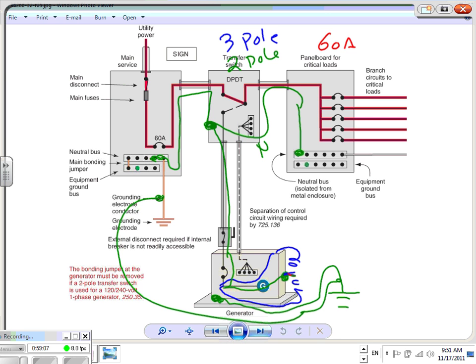A separately derived system. Any questions, guys, about this? Which one should I do? Either way. What's the advantage of doing it this way? Cheaper equipment. Instead of a 3-pole circuit breaker, you're using a 2-pole circuit breaker. Instead of a 3-pole transfer switch, you're using a 2-pole transfer switch. Cheaper equipment. Any questions?